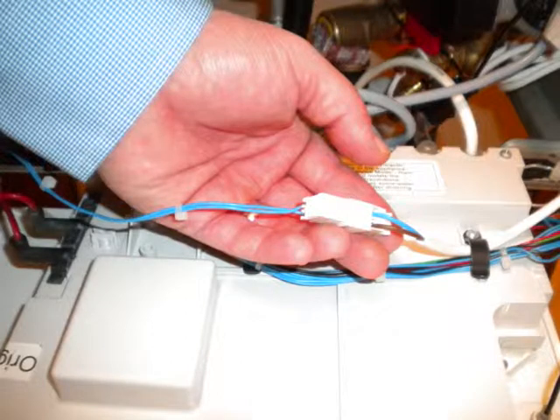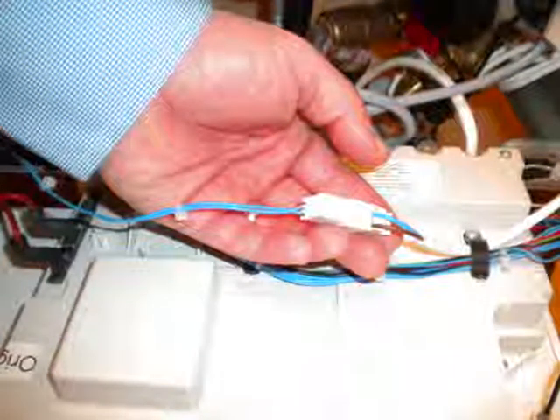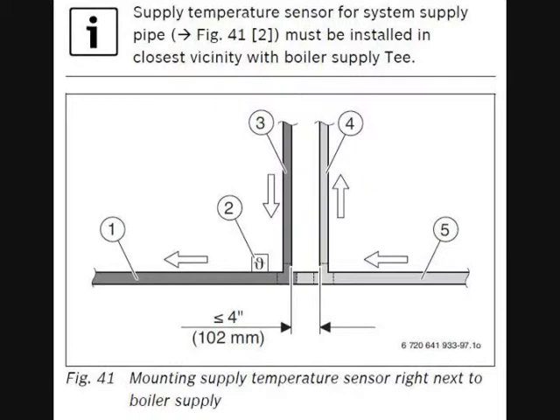Connect the system sensor. The system sensor connection point is located behind the control. Connect the blue and brown sensor wires to the white plug as shown in Figure 42 on page 54 of the install manual. As primary-secondary piping is the most common application, it is essential to install the system supply temperature sensor or the boiler will not function properly. Mount the system supply temperature sensor right next to the boiler supply T, as shown in Figure 41 on page 54 of the install manual.